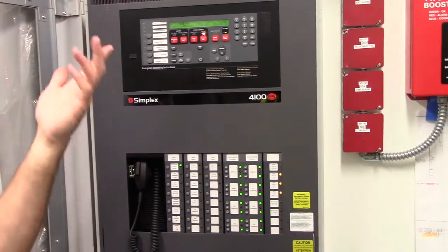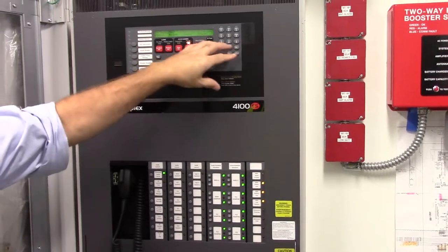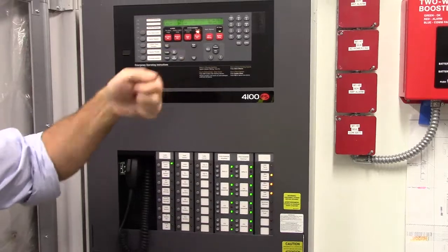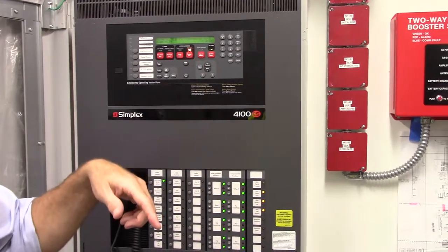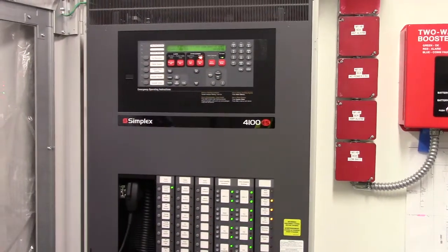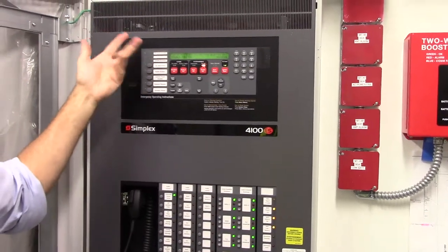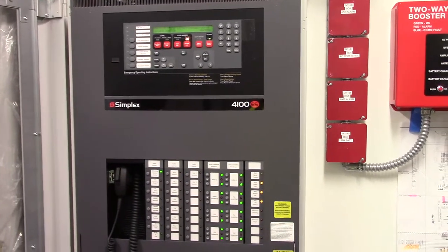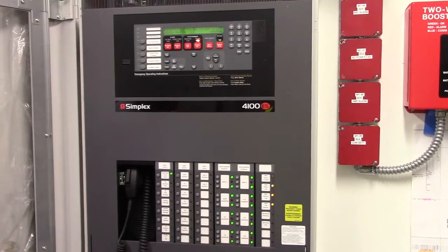I don't know if you wanted to go over the annunciator. It's basically the same exact setup. You don't have the individual display, the display is just this part of it. And you do need a key to operate anything from over there. So if you go to those panels, you can scroll through the troubles, but it won't let you acknowledge them without a key. Same thing with the bypass buttons along the side. You can press them, but unless you've got the key activated, it won't let you do anything. And I think that's pretty much it, unless you guys had any questions.